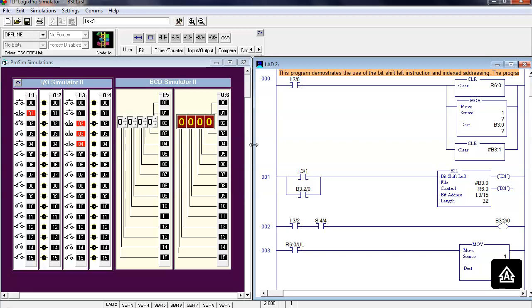These inputs are hooked up to some BCD switches, and we'll look at what's going on with this later on. So BCD means they only go from what? 0 through 9, right? Okay. What does BCD stand for? Binary coded decimal. So those guys are giving me BCD outputs, which means we're sacrificing 6 combinations, right? Binary coded decimal is not a weighted numbering system. Math in my PLC, we're going to do on a weighted numbering system, right? So we'll see later on how we can convert these.